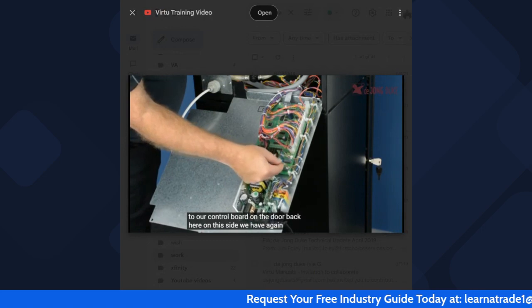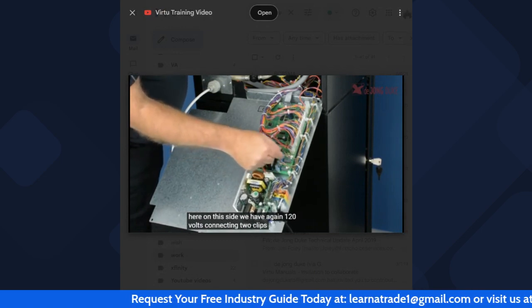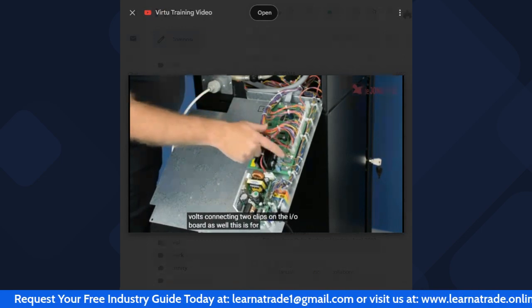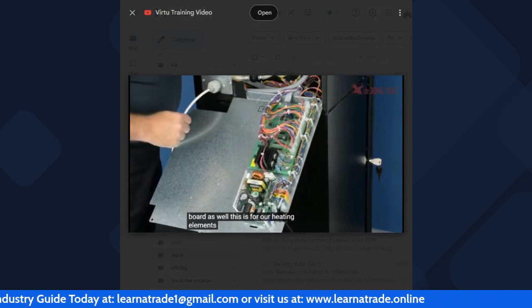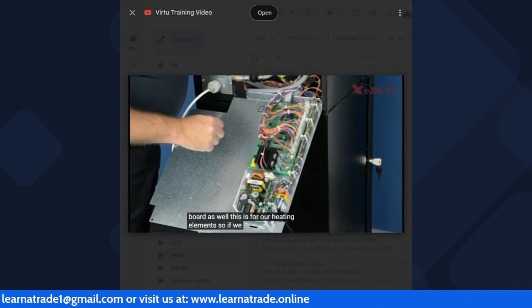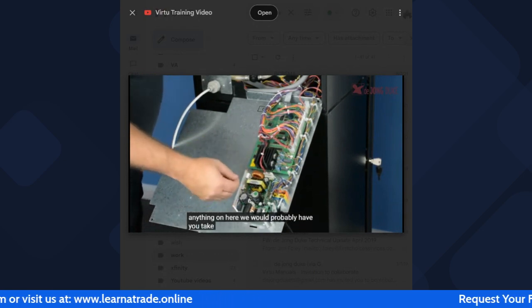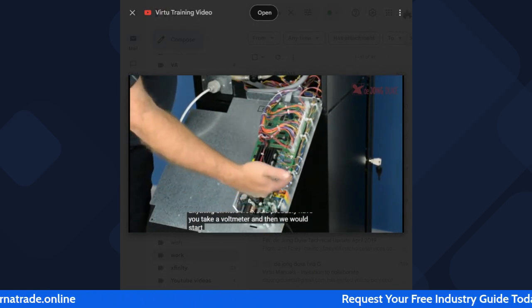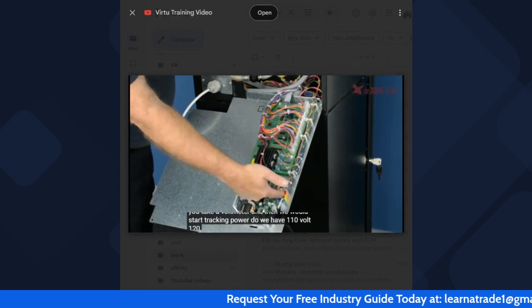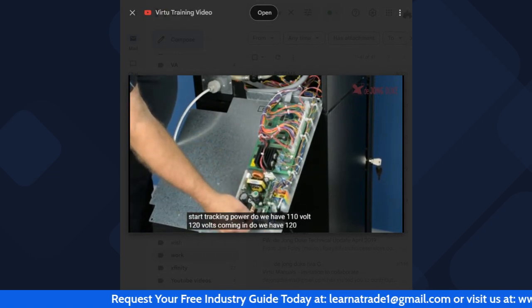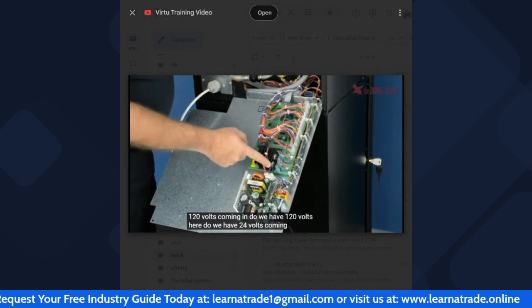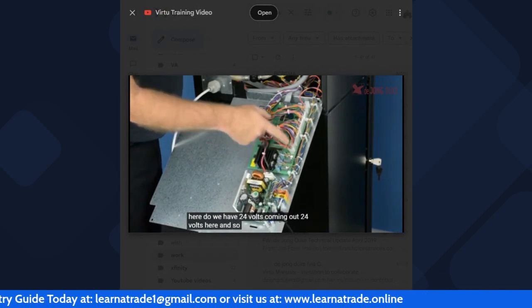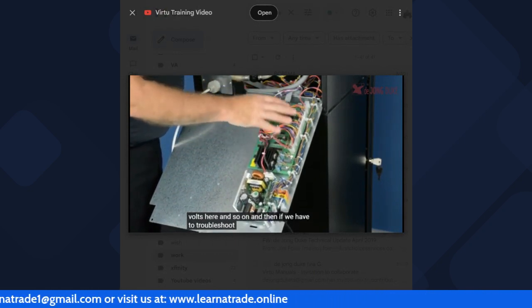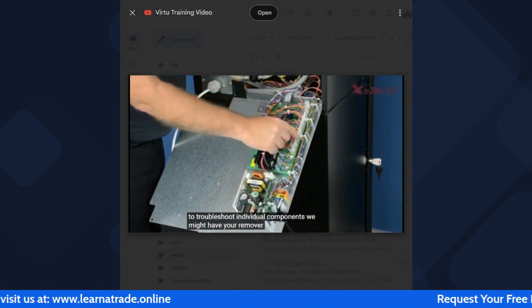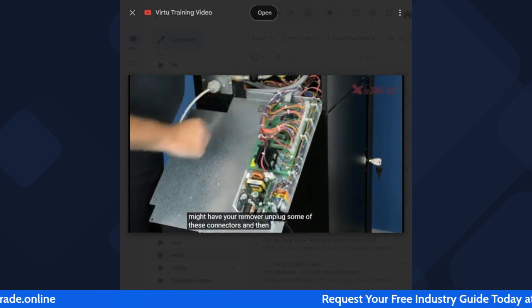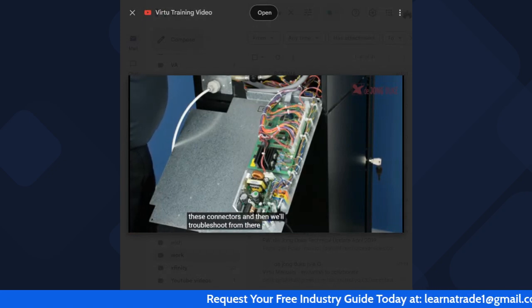Back here on this side, we have, again, 120 volts connecting to clips on the I/O board as well. This is for our heating elements. So if we have to troubleshoot anything on here, we would probably have you take a voltmeter, and then we would start tracking power. Do we have 110 volts, 120 volts coming in? Do we have 120 volts here? Do we have 24 volts coming out? 24 volts here, and so on. And then if we have to troubleshoot individual components, we might have you remove or unplug some of these connectors, and then we'll troubleshoot from there.